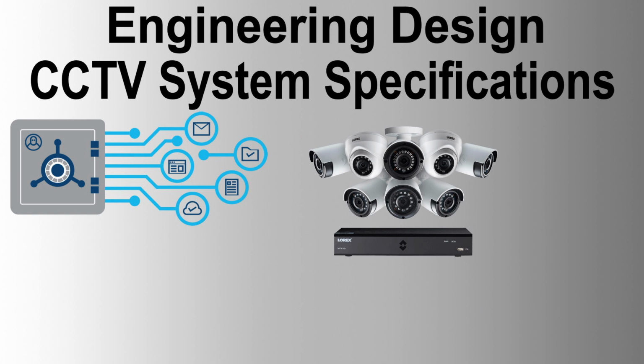System design requirements, general functionality, and system architecture. IP-based Ethernet network platform supporting full motion video images, comprising CCTV cameras, system cabinets, operator stations, and database servers. CCTV system cabinets, housing system equipment like FOC patch panels, video encoders, decoders, and Ethernet switches. Standard dimensions, freestanding type with cable entry from the bottom, equipped with necessary accessories for proper ventilation and protection.